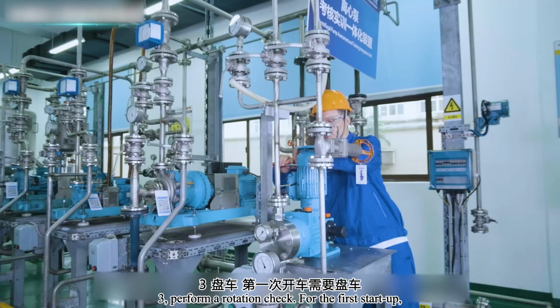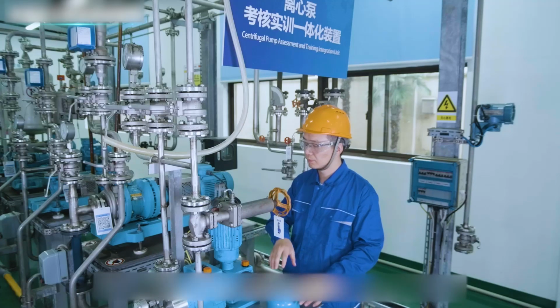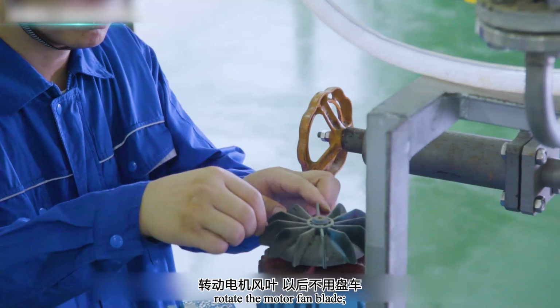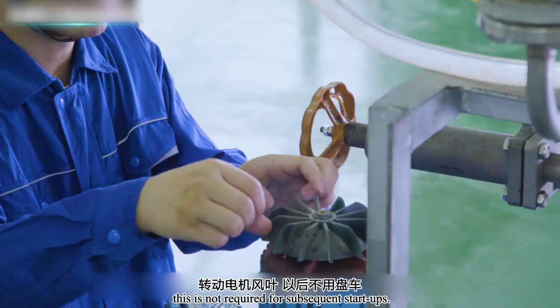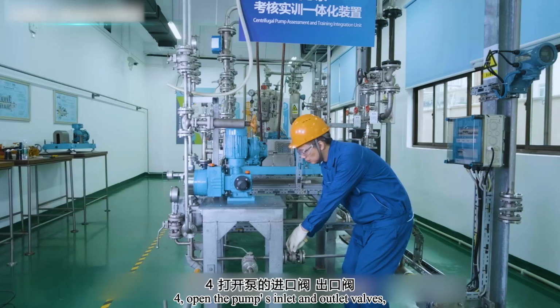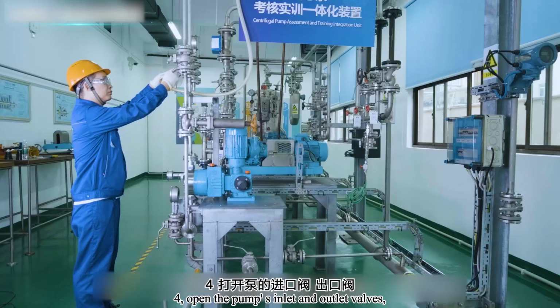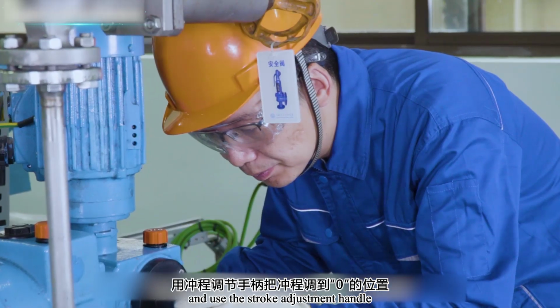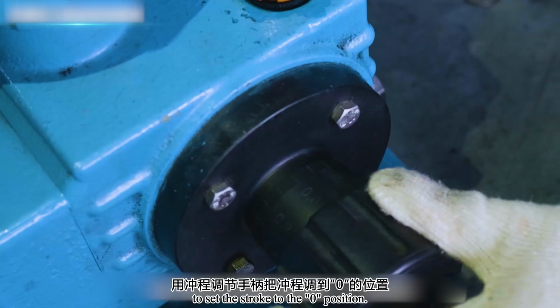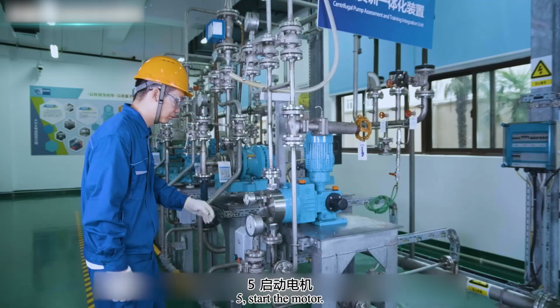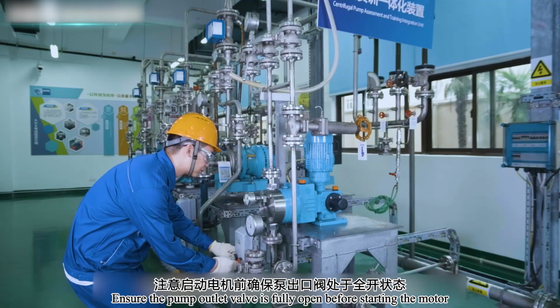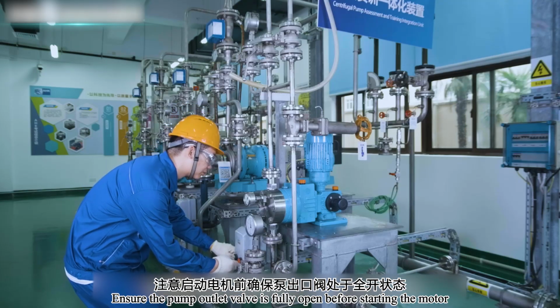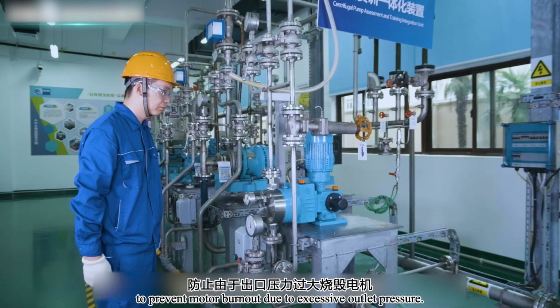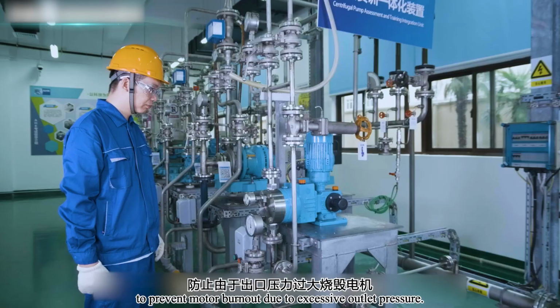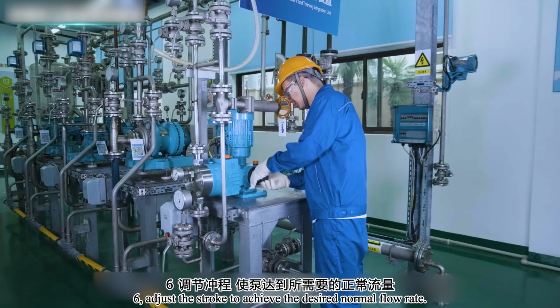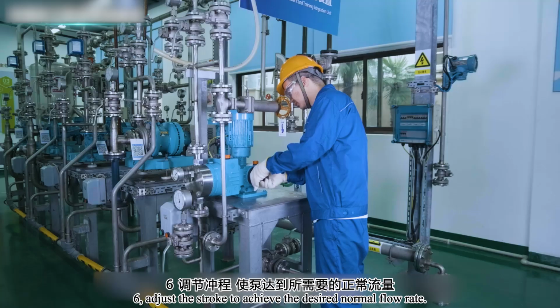Third, perform a rotation check for the first startup. Rotate the motor fan blade. This is not required for subsequent startups. Fourth, open the pump's inlet and outlet valves and use the stroke adjustment handle to set the stroke to the 0 position. Fifth, start the motor. Ensure the pump outlet valve is fully open before starting the motor to prevent motor burnout due to excessive outlet pressure.